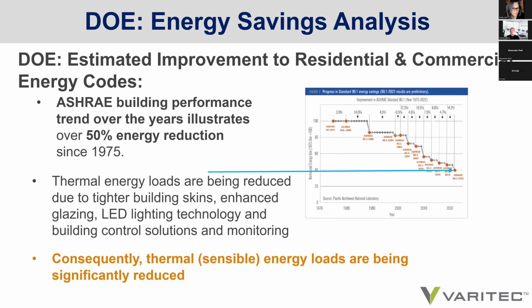So it begs the question, as buildings are becoming more efficient and thermal energy loads are being reduced due to tighter building skins, enhanced glazing, LED lighting, etc., airflows are going to be reduced in order to meet our peak summer design days. Certainly in Maricopa County, where we design to 115, now 120, perhaps maybe even 122 as the future goes. Well, in the old days, when buildings leaked significantly, a large amount of airflow was required to maintain the thermal energy load.